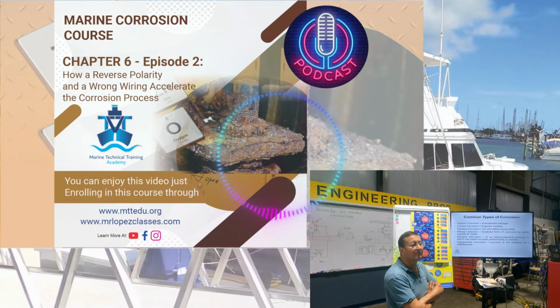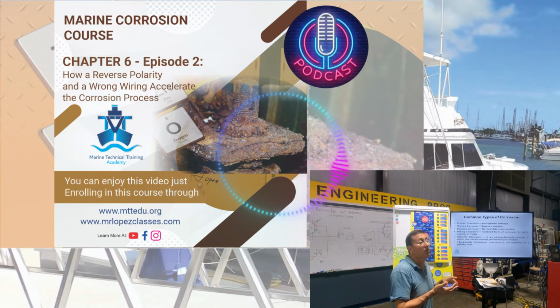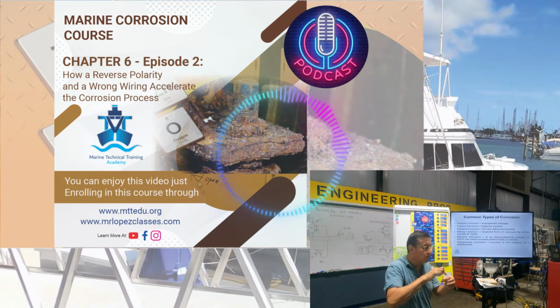Okay, let me explain how the wiring is in the back of those three breakers when you use three individual breakers instead of the switch selector. This is the procedure. This is the shore power, the pedestal, and the pedestal produces, in this particular example, double phase and neutral: phase 1, phase 2, and neutral.